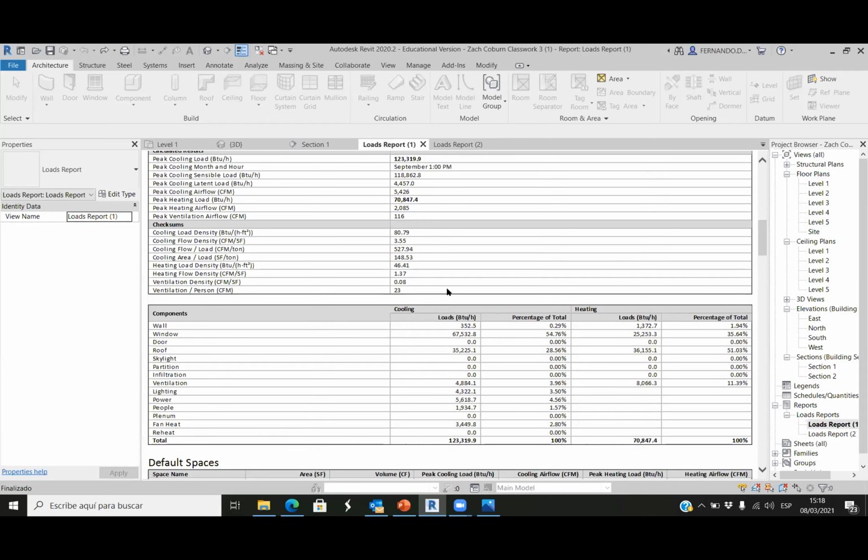So there is a moment in which, when we meet the passive house standards in walls and roofs, that's it. Yeah, we can add, instead of 8 inches, we can have 16 inches or 20 or 50 inches, and probably we reduce this from 300 to 200. That's fine. But if we analyze this, we have 67 and 300. So first, we need to solve this, because we have 67,000 here and only 300 here. So the issue is in the window, it's not in the wall.